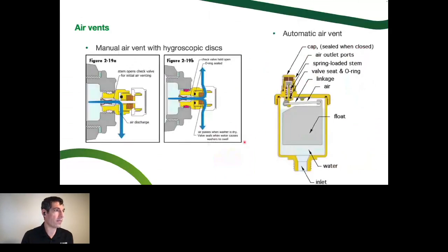The way that an air vent works, an automatic air vent with a float style, we have some that you would go into a radiator or something to just bleed a little bit of air out of the top of a radiator. The way that an automatic air vent works with a float is, as that air gathers at the top, it allows this float to drop. It opens this little needle valve and it allows air to come out. Then as the air escapes, the float comes back up.